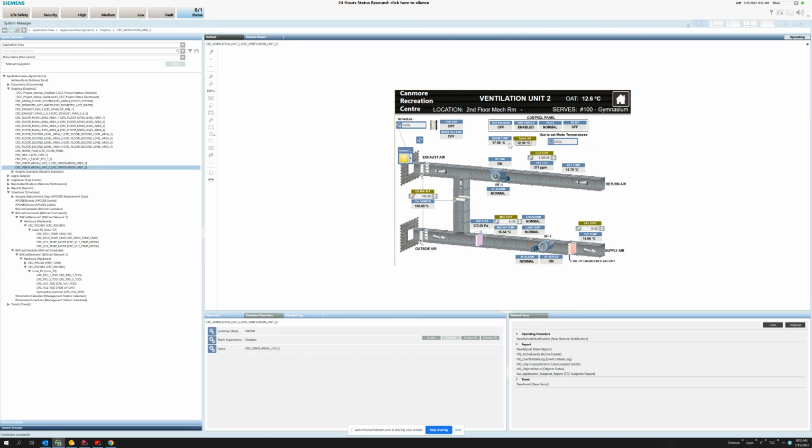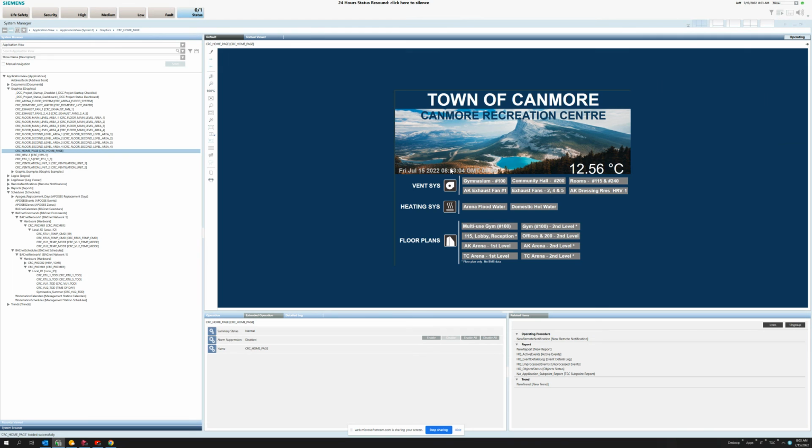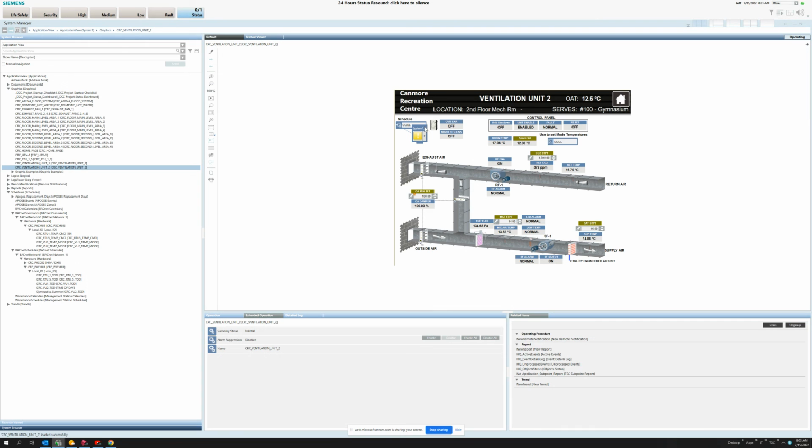I know 12 degrees seems like a crazy low temperature to ask for, but since this room doesn't have air conditioning, that's why the schedule is currently set to cool overnight and unoccupied during the day, because when it's going to be plus 30 out, it's the only way to keep that space at a reasonable temperature. If it's 30 degrees and we start off really cold in the morning, it tends to stay in the low to mid 20s through the day, even when the sun's on it. So it's a reasonably effective way of dealing with the lack of air conditioning. I think that covers it.